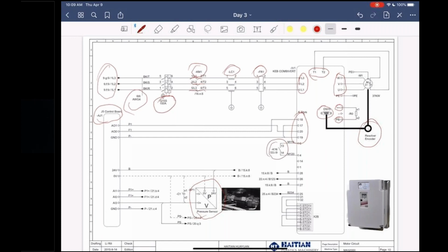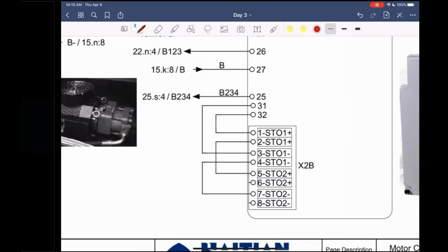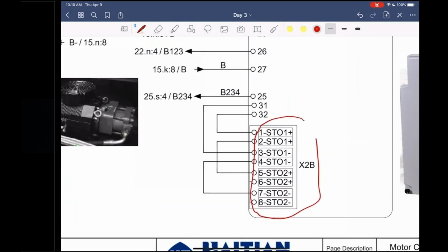This K16 goes to the safety relay, and that makes sure that if there's a problem with the safety circuit, the drive will not start. These STO inputs also come from the safety relay, and if you have an electric machine, it'll tell you that there's a STO, mold close STO, or some other STO error. Unfortunately, on the Mars machines, you do not get the STO errors, but it is caused by the safety circuit not being satisfied.